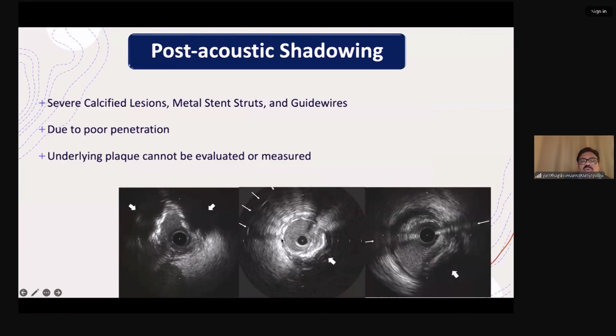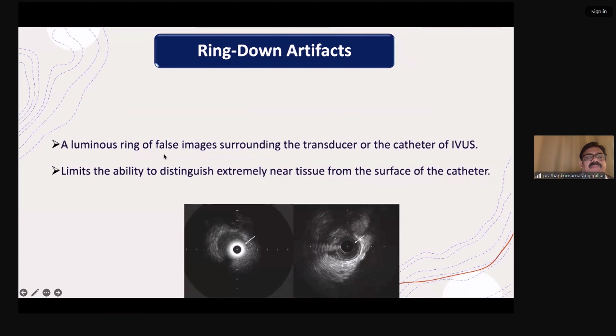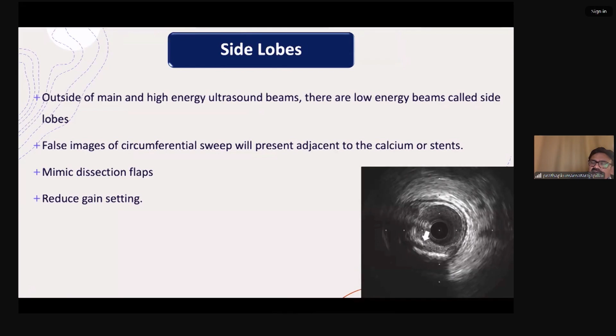Ring-down effect is usually with the Philips machine, and is not common or almost nil with the Boston Scientific. A luminous ring or false images surround the transducer. Side lobes: outside the main high-energy ultrasound beam, there are low-energy beams called side lobes. A false image of circumferential sweep will be present adjacent to the calcium or stent. It can mimic a dissection flap, or reduce gain setting.